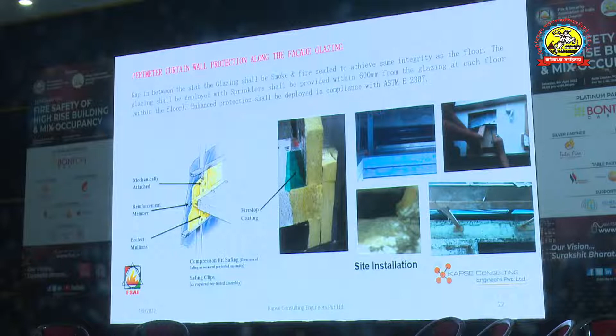Re-entry to stairs, I just discussed. Passive fire protection: this is the most important aspect of curtain wall protection. People have glazed buildings these days, they want very high-rise glazed buildings with partitions, but the gap between the slab and the facade is not protected. 90% of buildings are not protected. They do some patchy work, and this transports the fire from floor to floor. This is one of the most critical aspects. You can have a ventilated panel.